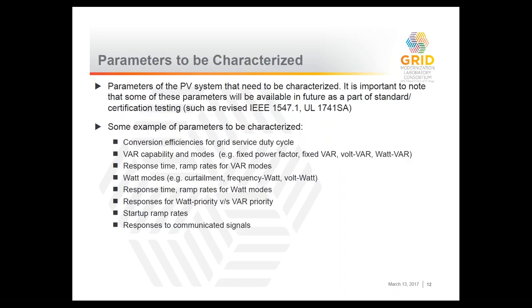But then there are some other parameters that need to be characterized to come up with that model. Now, a disclaimer here: as of today, there is not as much certification testing available for some of the advanced smart inverter functions, except the California work with UL to develop UL 1741 SA, which is looking into some of those advanced functions. So it's still not there, but once we have some of those done by a certification test body like UL, then we can get some of those parameters from the certification testing, such as VAR capability mode, response time for the VAR, Watt modes, their response time, startup ramp rates, and things like that.